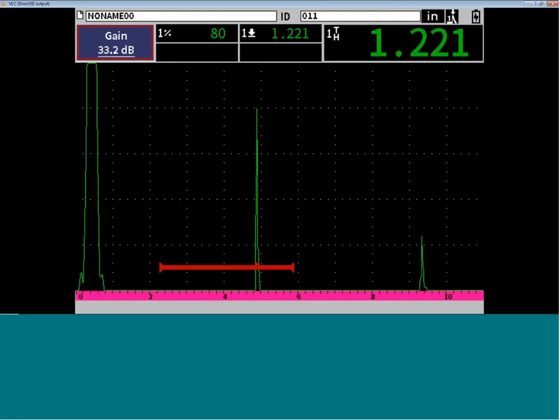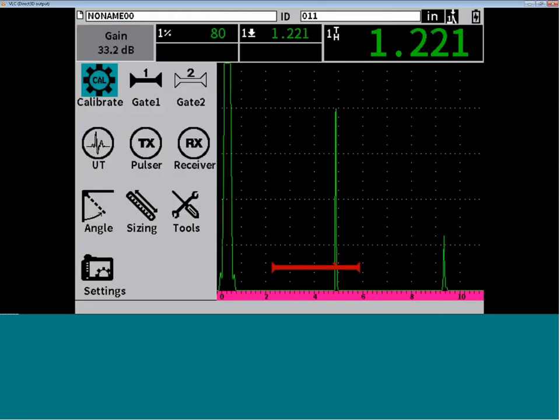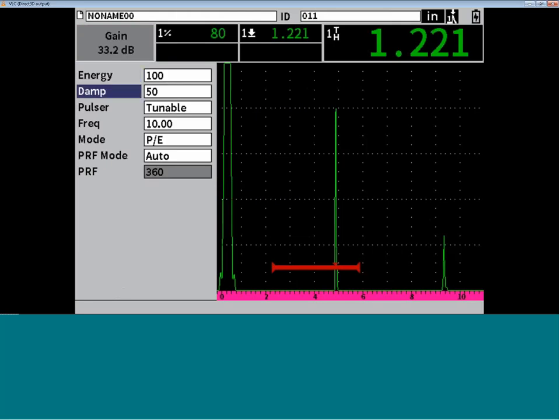But for things like calibration of the unit, setting up the sizing techniques such as DAC, we do have a separate screen for this, and this is our split screen mode. So we go away from the full screen A-scan, and now, again from the left side of the screen, we have a menu area that allows you access to deeper control of the instrument. Olympus is focused on trying to provide both written labeling for what these categories are, but also a very easy icon system, so that it's very fast to identify the controls that you want to make adjustments to and actually achieve results within those controls. As an example, if we wanted to adjust our pulser settings, we would highlight this pulser icon and press the Enter key. And now we have access to all of our major pulser settings, including energy, damping, and the frequency of our tunable pulser.